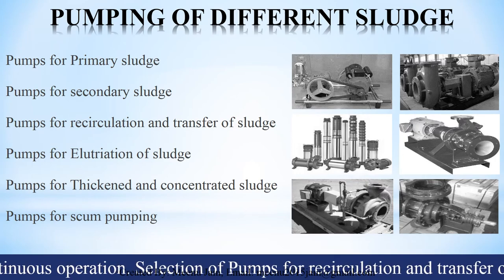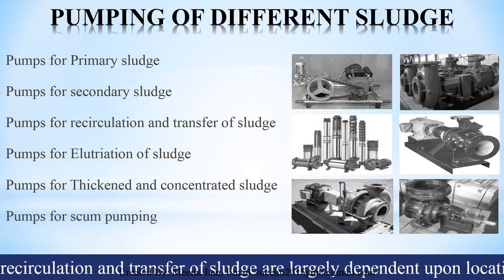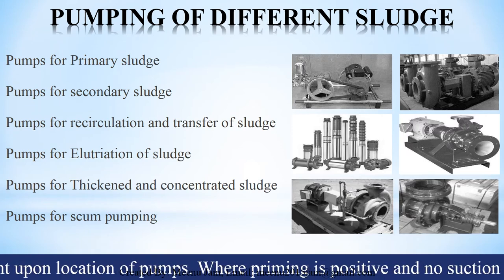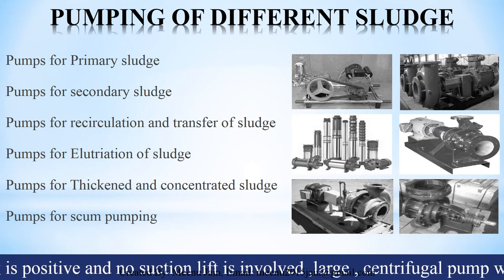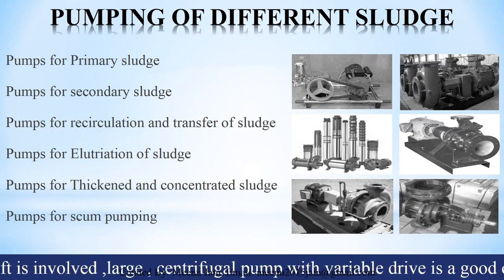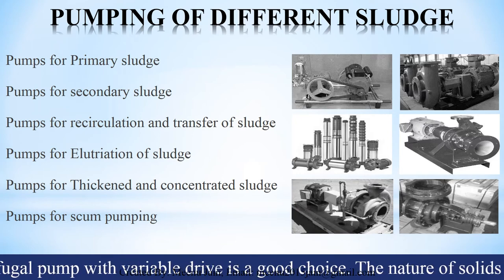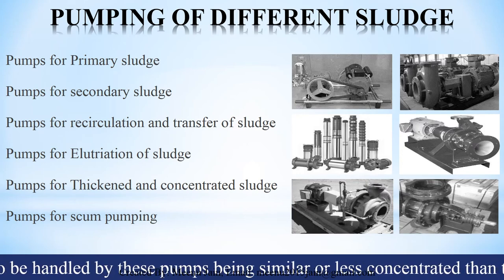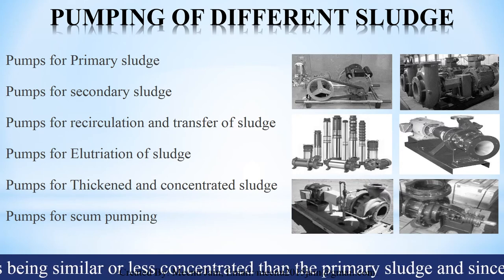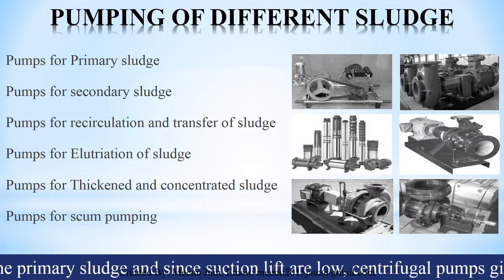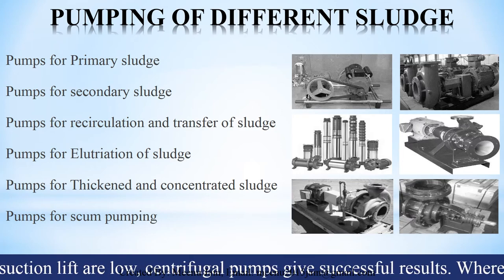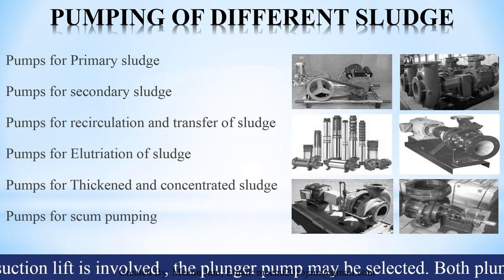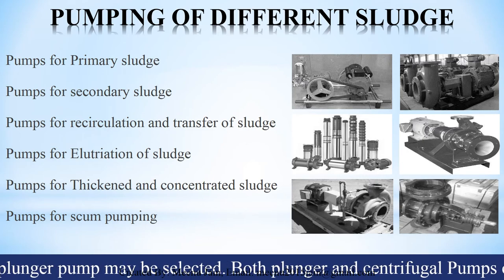Selection of pumps for recirculation and transfer of sludge is largely dependent upon the location of pumps. Where priming is positive and no suction lift is involved, a large centrifugal pump with variable drive is a good choice. The nature of solids to be handled being similar or less concentrated than primary sludge, and since suction lifts are low, centrifugal pumps give successful results. Where suction lift is involved, plunger pumps may be selected.